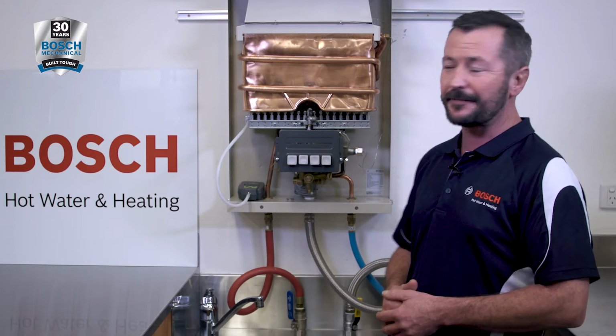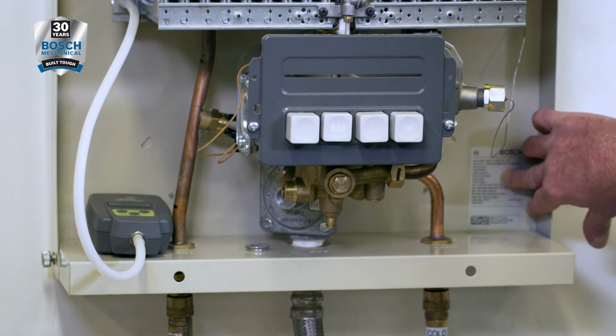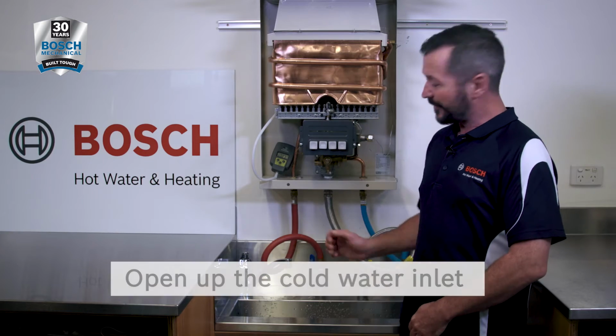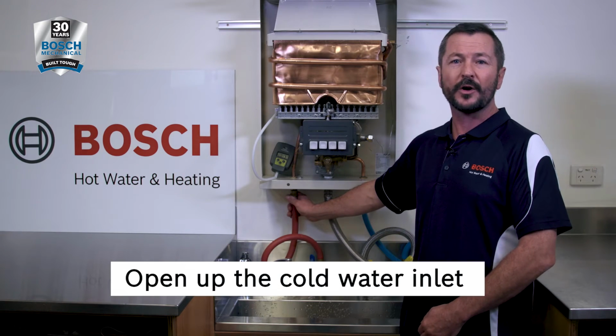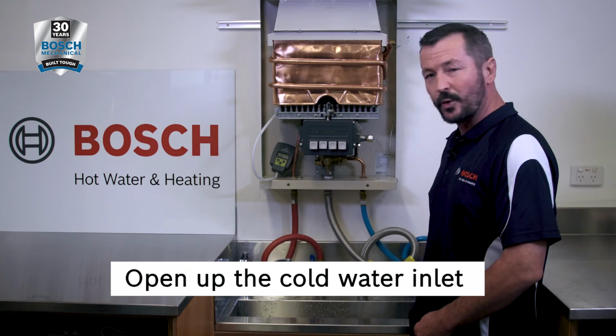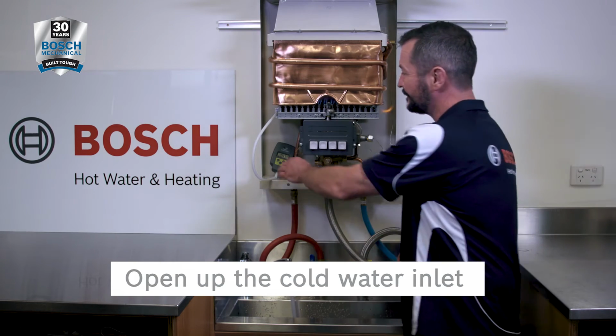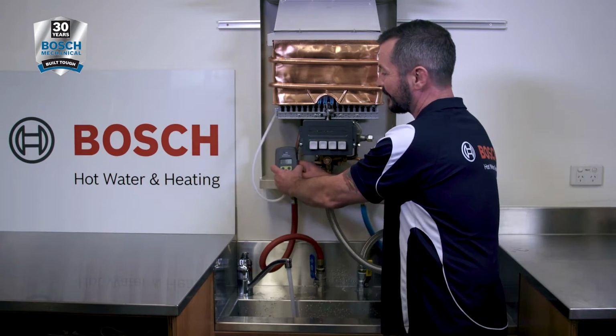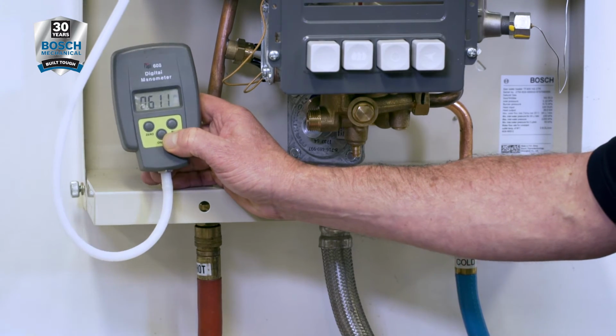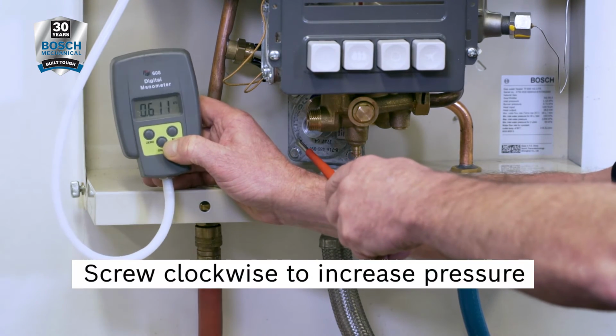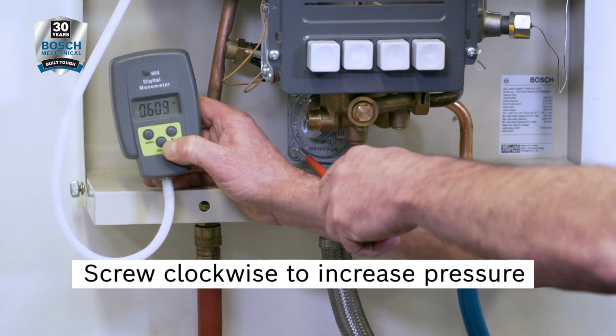The burner pressure can be found here on the data plate and also in the instruction manual. With your hot water outlet disconnected or a full flow hot tap open inside, open up your cold water inlet and check your burner pressure. The maximum burner pressure is also adjusted via the appliance regulator. Winding the adjustment screw in clockwise will increase the pressure, anti-clockwise will decrease the pressure.